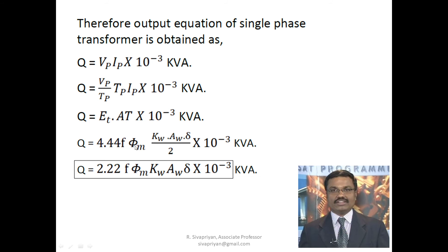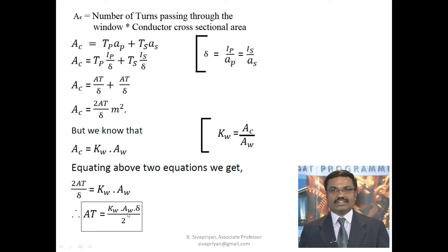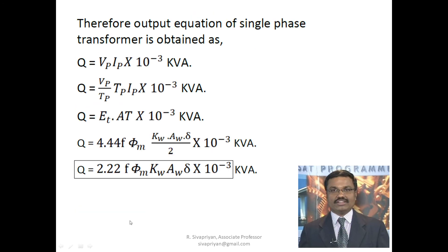The EMF per turn Et equals 4.44×f×φm, and AT equals (Kw×Aw×δ)/2. Substituting these values: Q = 4.44×f×φm × (Kw×Aw×δ)/2 × 10⁻³. The factor 4.44 divided by 2 gives 2.22, so the output equation becomes Q = 2.22×f×φm×Kw×Aw×δ×10⁻³ kVA.